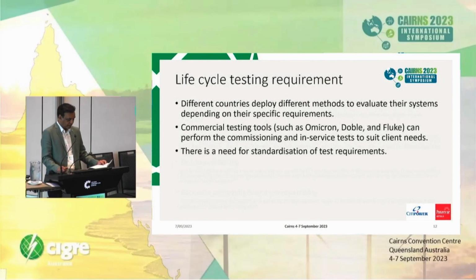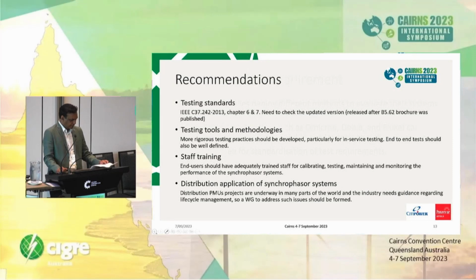Now, in the examples we saw from different countries, each one of them has deployed evaluation methods to test their specific requirements using commercial test tools such as Omicron, Fluke, or Doble. But having a standard to define the requirement for life cycle testing will actually make evaluation much simpler. In the recommendations of the report, we recommended the following. So, Chapter 6 and 7 of the IEEE C37.242 standard should be followed until a dedicated testing standard is released. End-to-end testing practices should be better defined.